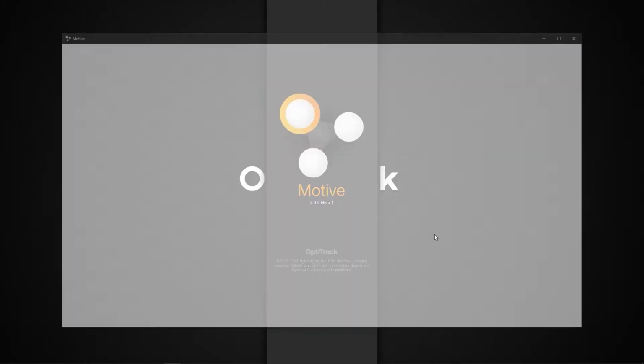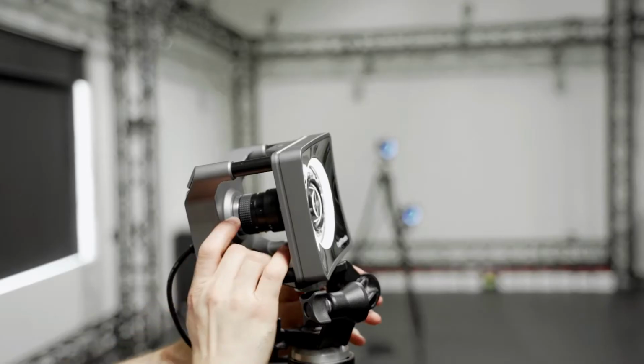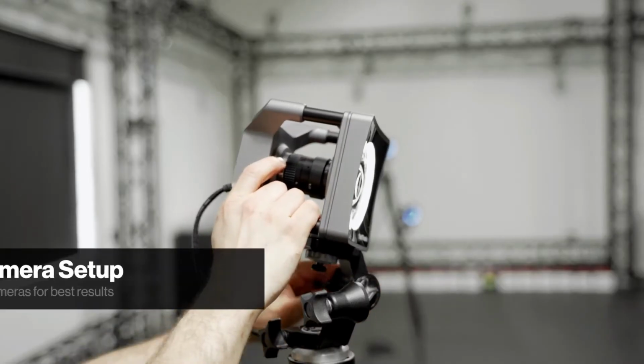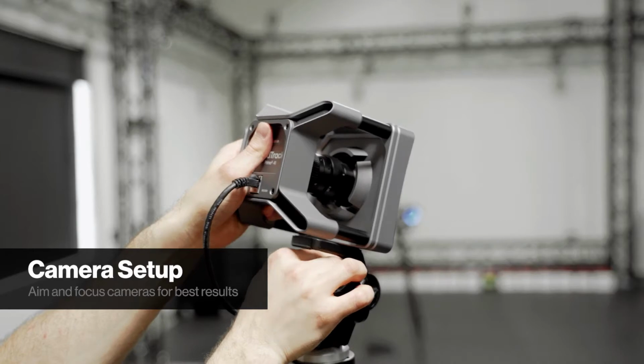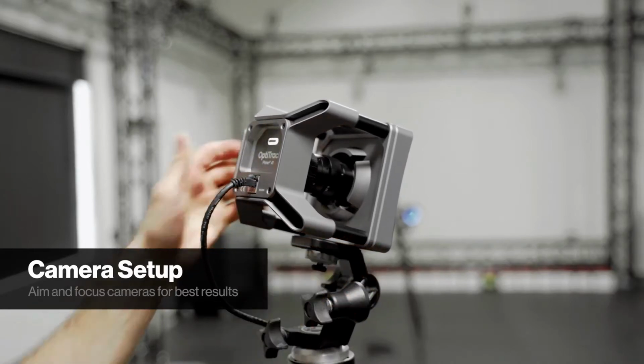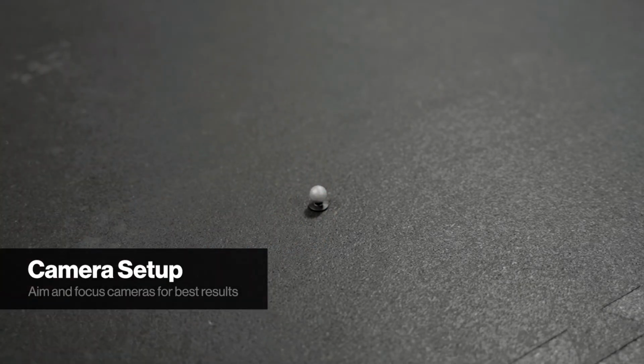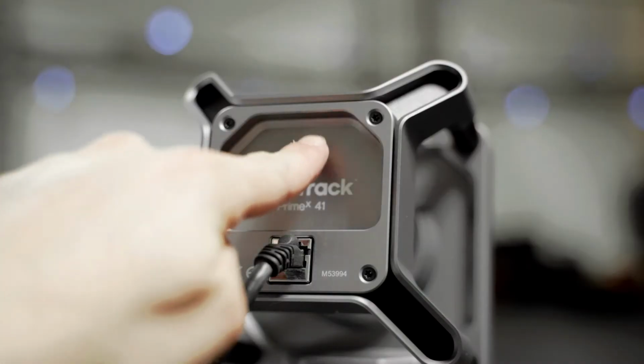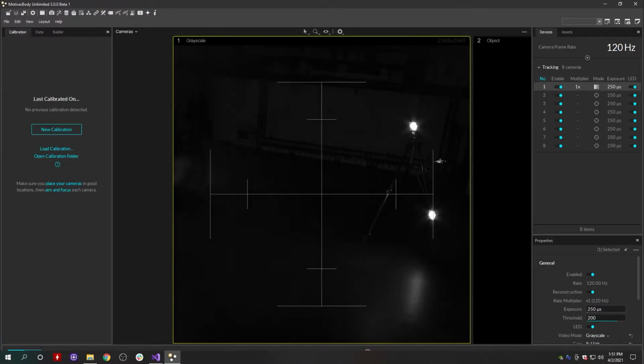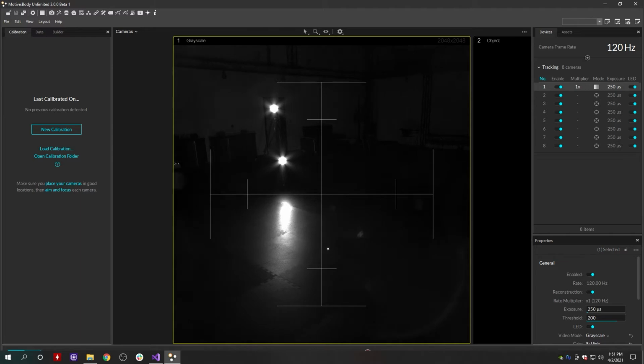Now that Motive is running, you can start camera configuration. The first thing you will need to do is aim each camera. We recommend setting up a TV, monitor, or your phone to remotely reference Motive. Place a few markers in the target capture area for reference points when aiming and focusing. Single-click the Aim Assist button on the back of each camera to switch that camera into grayscale mode and center that view in the monitor.